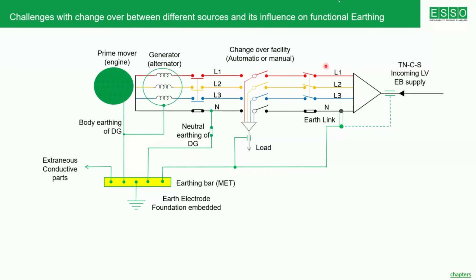One of the challenges which most of the hospitals are facing is the challenge with changeover between different sources and its influence on functional earthing. You are seeing a picture from IS 3043. You have the engine, or you have the generator, which has got an engine and an alternator. Then you have the mains supply, TNCS supply. You have an automatic changeover, and the changeover you can see here with a 4-pole switch.